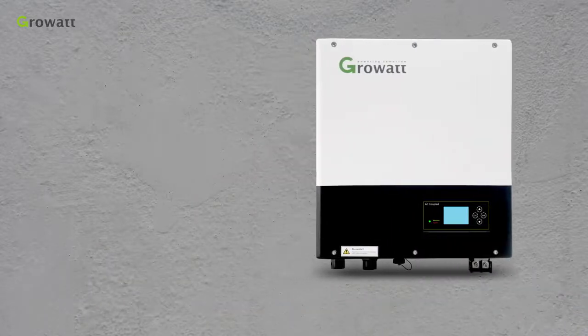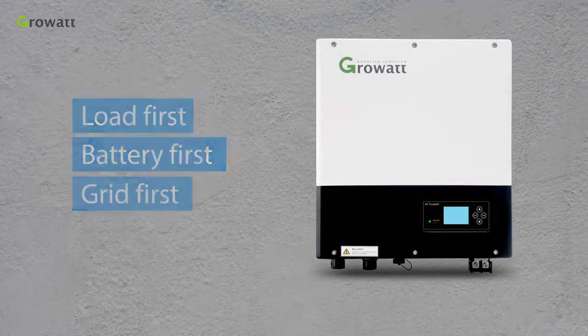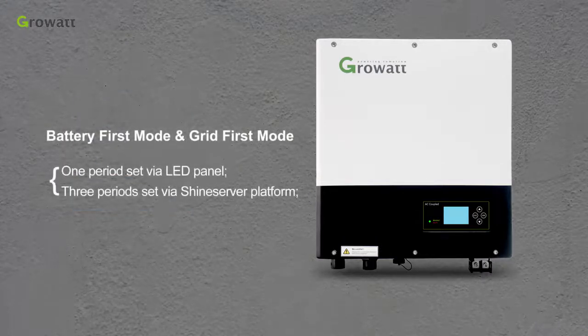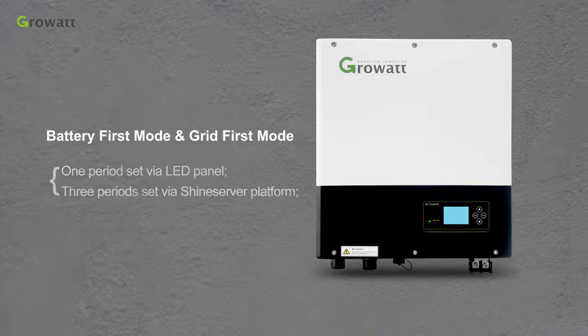SPA can be used in different mode. Load First, Battery First and Grid First. For Battery First and Grid First mode, customer can set the timetable for it. Through LCD can set one time period. Through GrowWatt Shine server can set three time periods each.